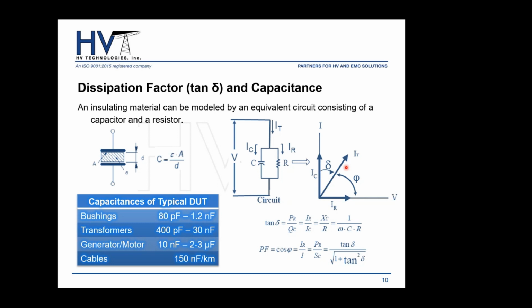But as you can appreciate in this vector diagram, the angles are complementary. You have tan delta here and cosine phi over here, and they are complementary. So when you have a small tan delta, you basically will have the same value if you take the cosine of this larger phi angle. So for these small insulation measurements, we can say that basically tan delta and power factor are more or less giving the same information.